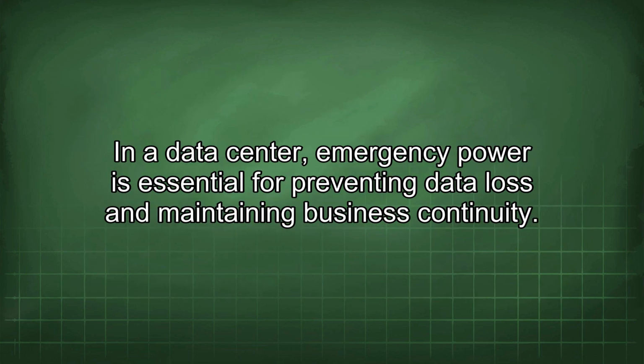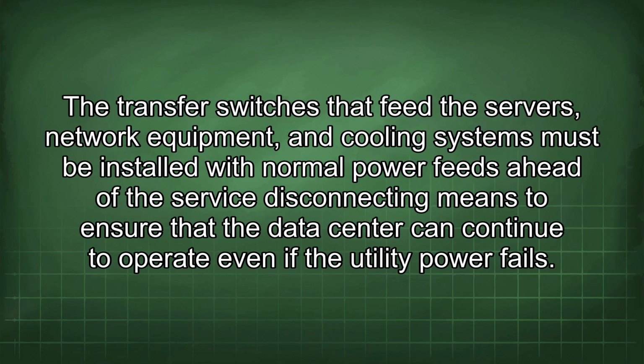In a data center, emergency power is essential for preventing data loss and maintaining business continuity. The transfer switches that feed the servers, network equipment, and cooling systems must be installed with normal power feeds ahead of the service disconnecting means to ensure that the data center can continue to operate even if the utility power fails.